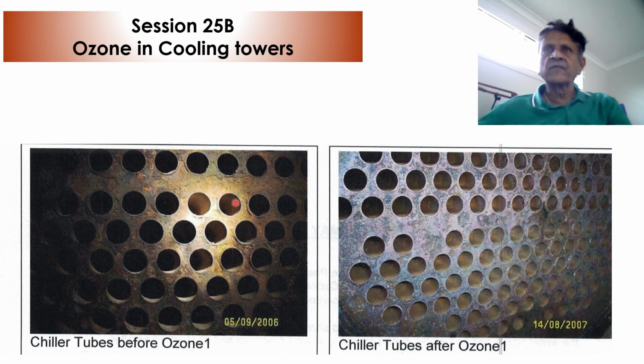You will see, in fact, the best we cleaned before, but once ozone has been applied, the chiller tubes have become cleaner than even our original clean chiller tubes.